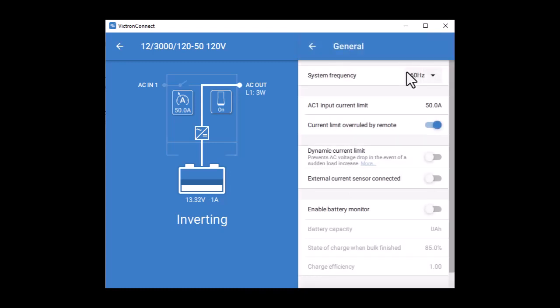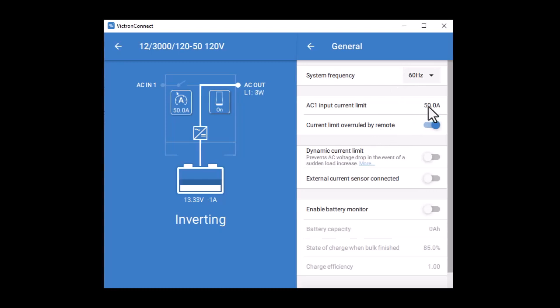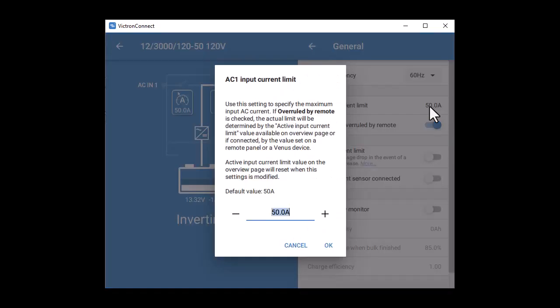Here we get to verify the system frequency and voltage and the AC input current limit. The AC current limit is the total amount of incoming AC power. Typically, in a 120 volt system, it will be either 30 amps or 50 amps. When you check the overrule by remote button, it allows you to change the setting on the fly using your remote panel as you move from place to place. My system is just a demo, and the only available place to plug in is a wall outlet, so I'm going to set my limit to 15 amps.